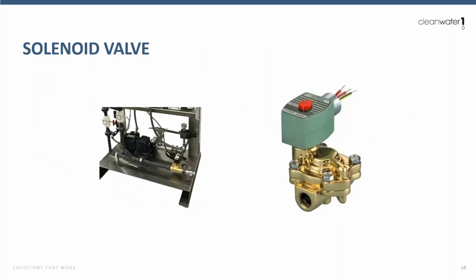The solenoid valve. So when we were talking about water quality and different items as far as water quality goes, solids is one of those things that came up, right? So the solenoid valve is responsible for turning on and off water flow to the system itself. One thing that's important to note here is that buildup can happen within these solenoid valves if there's a high amount of solids in the water. And what can happen is that plunger can get stuck open. So these will fail open. And basically, it eliminates your ability to shut the water flow off unless you have an isolation valve upstream.